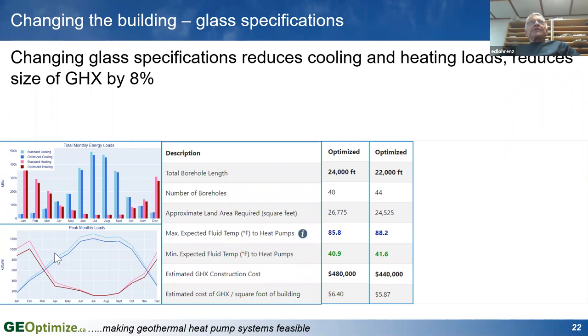For example, this first building is looking at just changing the glass on the building. What that does is drop the cooling loads compared to the original building, as well as drop the heating loads, because this glass that was selected had better insulating quality. So that changes the amount of heating that you need. And in this case, it dropped the amount of borehole that you needed from 24,000 feet of drilling down to about 22,000 feet of drilling, saved about $40,000, and kept the temperature range fairly similar.